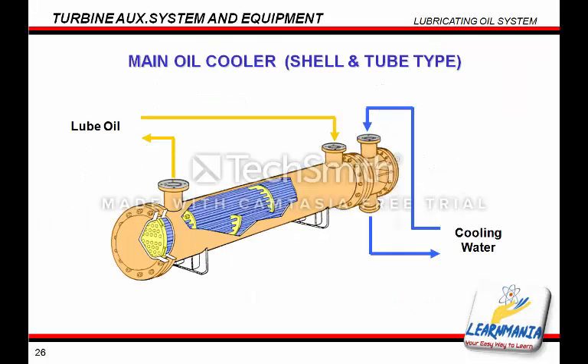This figure shows the second type of oil cooler used. Cooling water passes through the tubes and oil flows around them. Usually, the pressure of oil in the cooler is higher than that of the cooling water. Therefore, even if a tube is damaged, cooling water does not enter the oil. The oil coolers described previously utilize the same principle.